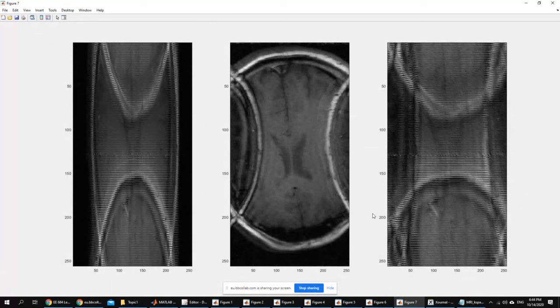So when you have fewer points, for example, instead of 1,000 you have 500, you collected the data in half the time. So in theory, you should have the image in half the time of the original. The problem is, if this reduction in samples resulted in aliasing, then you lost everything. You have to repeat the image with the correct sampling. These images are not acceptable.